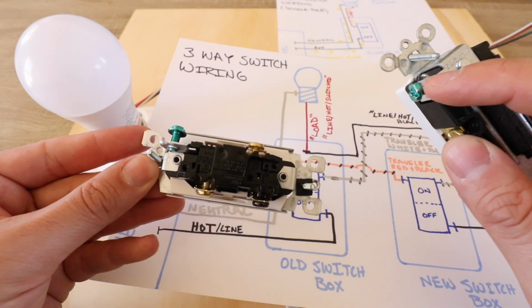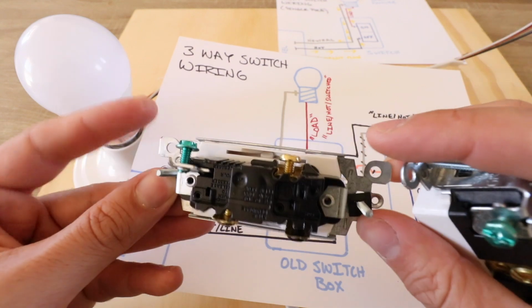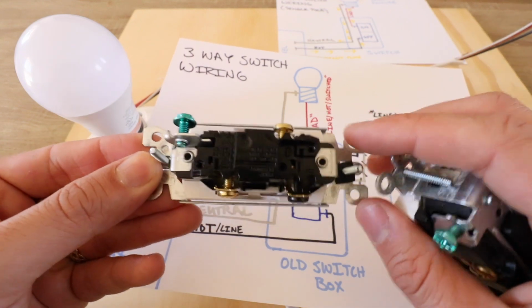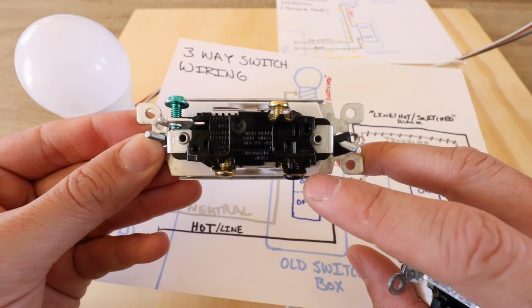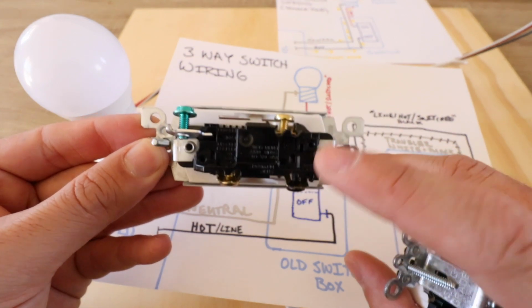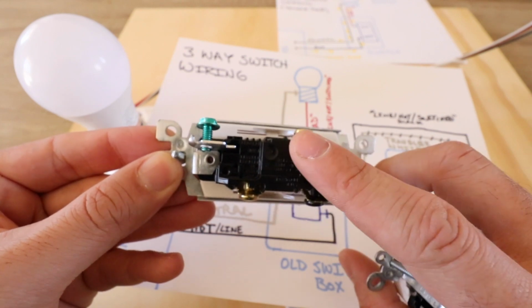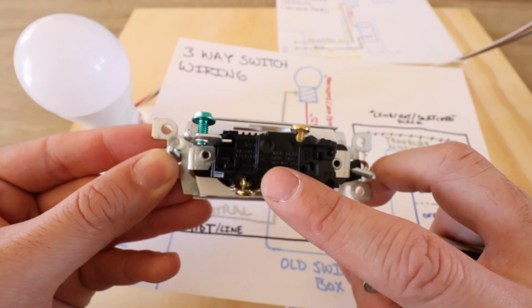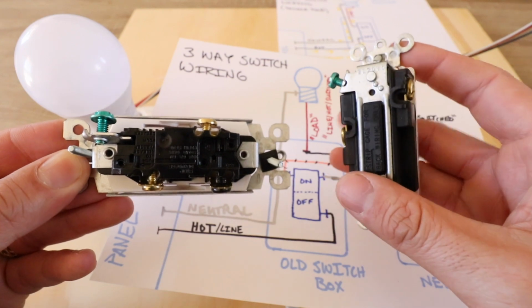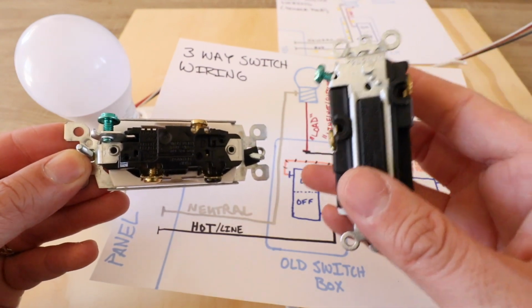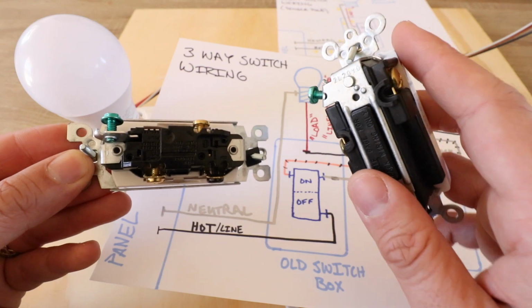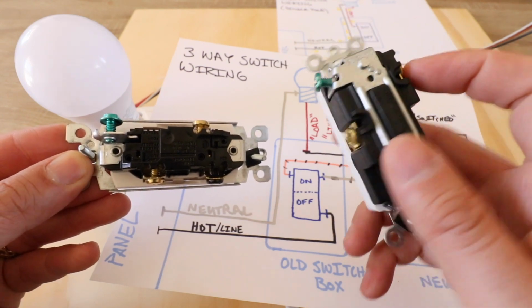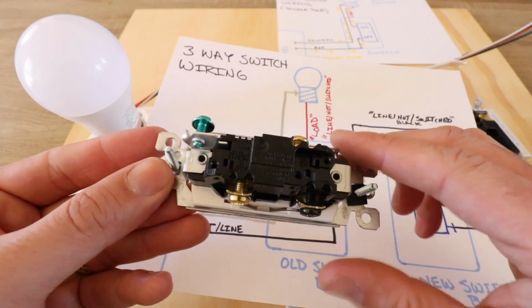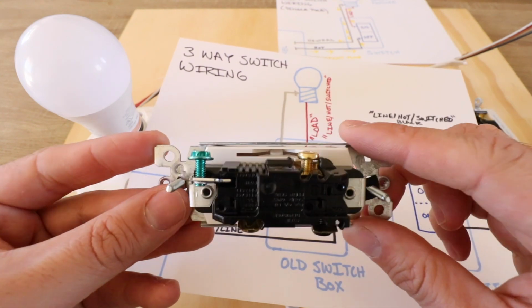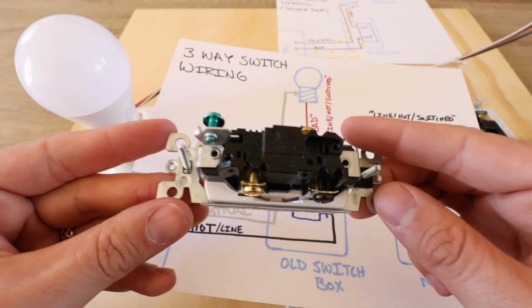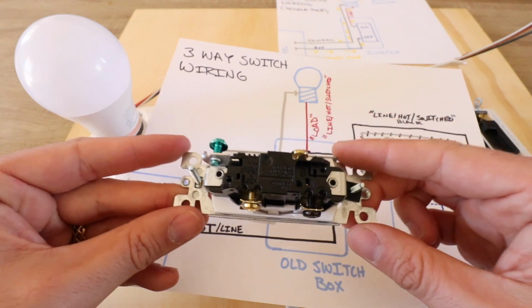Now you might say, what's this extra screw? That is the ground screw, and you've got a ground screw on this one as well. So when you have a three-way switch, you're going to have a hot or line terminal, and then you're going to have what are called two traveler terminals, and that's these brass terminals here. And like we showed you on the traditional single pole switch that is not three-way capable, it does not have those extra terminals. It just has two terminals. So that's the first difference with a three-way switch. You have three terminals on each switch, so you're going to need to buy specific three-way light switches.